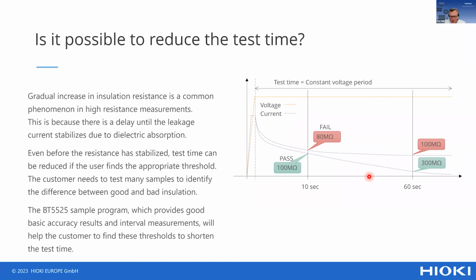Yeah. What I would like to recommend, if you look at this pass in this graph, you see that the 10 seconds is basically the start of the linear part of the increase of the resistance measurement. So it would not be wise to use a point which is earlier than this 10 seconds, but in other situations, in other cells, it might be that you start this linear part at an earlier stage, but that's depending on the cell that you are testing, to decide how long you want to measure to make sure that you have a good indication of the insulation resistance of your cell. Okay.